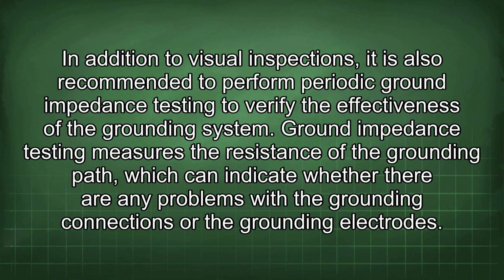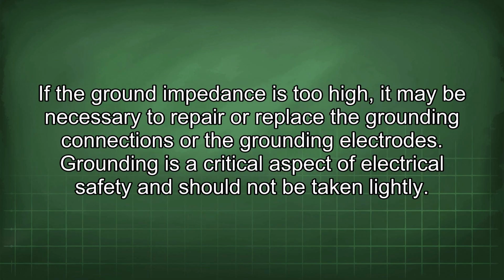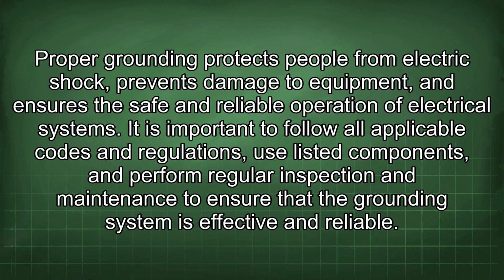In addition to visual inspections, it is also recommended to perform periodic ground impedance testing to verify the effectiveness of the grounding system. Ground impedance testing measures the resistance of the grounding path, which can indicate whether there are any problems with the grounding connections or the grounding electrodes. If the ground impedance is too high, it may be necessary to repair or replace the grounding connections or the grounding electrodes. Grounding is a critical aspect of electrical safety and should not be taken lightly. Proper grounding protects people from electric shock, prevents damage to equipment, and ensures the safe and reliable operation of electrical systems. It is important to follow all applicable codes and regulations, use listed components, and perform regular inspection and maintenance to ensure that the grounding system is effective and reliable.